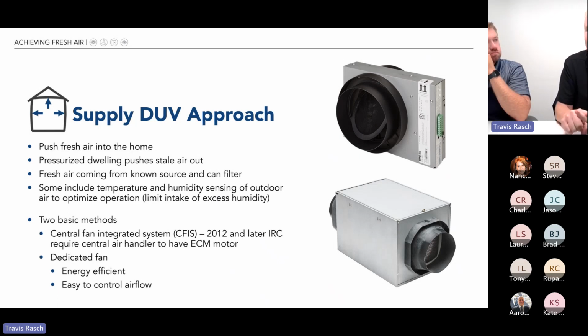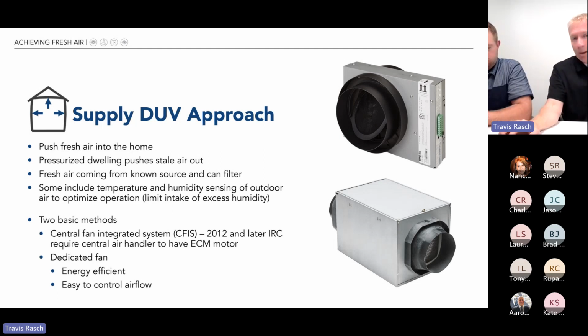Secondly, you can really control the airflow. We've heard stories that with a CFIS system, when they check these out and verify them, they're not getting that 55, 60, in larger homes even more than that. They're just not getting that airflow. So with a dedicated fan inside that housing, you can set it for 60, 75, 90, whatever you need, and you know you're going to get that. So you don't have to worry about not passing at the 11th hour on your airflow verification.